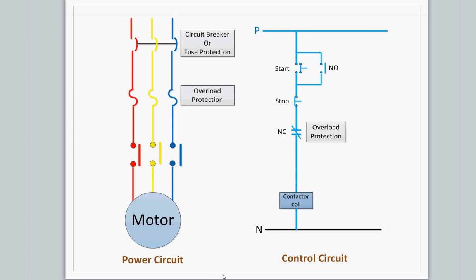This shows the power and control circuit of the DOL starter. So basically it gets the three-phase power and the circuit breaker or fuse. It can be used for protection in case of motor failure or short circuit. Then there is an overload protection here, and then these are the contacts of the contactor, and as said earlier, all three-phase voltage is applied to the motor directly.